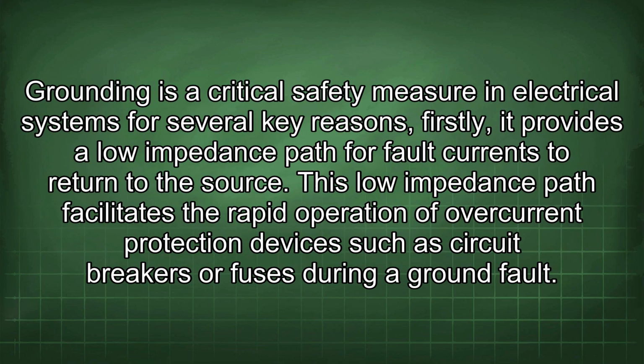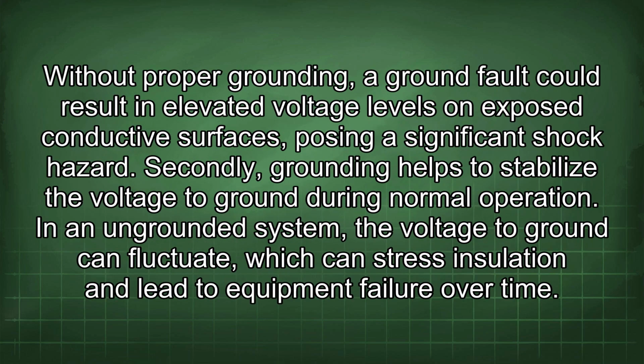Grounding is a critical safety measure in electrical systems for several key reasons. Firstly, it provides a low impedance path for fault currents to return to the source. This low impedance path facilitates the rapid operation of overcurrent protection devices such as circuit breakers or fuses during a ground fault. Without proper grounding, a ground fault could result in elevated voltage levels on exposed conductive surfaces, posing a significant shock hazard. Secondly, grounding helps to stabilize the voltage to ground during normal operation.